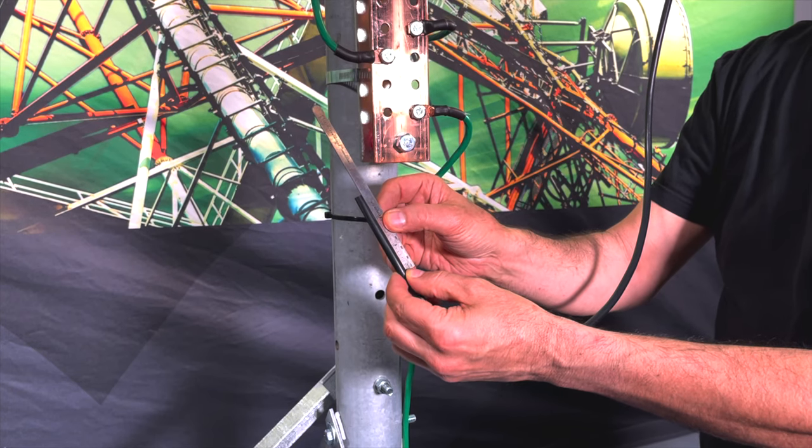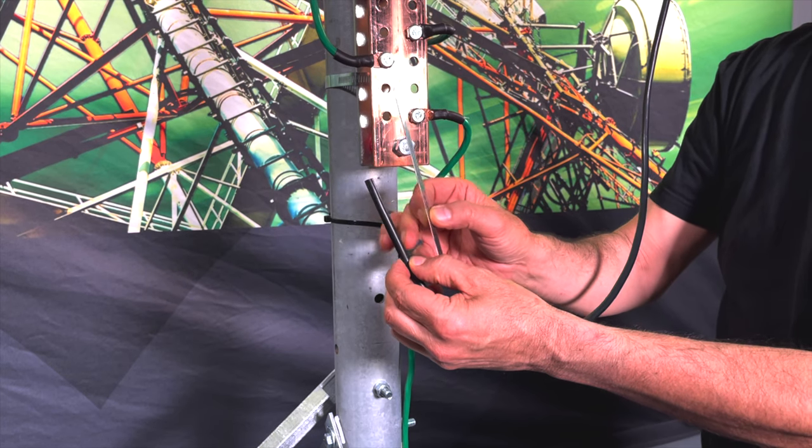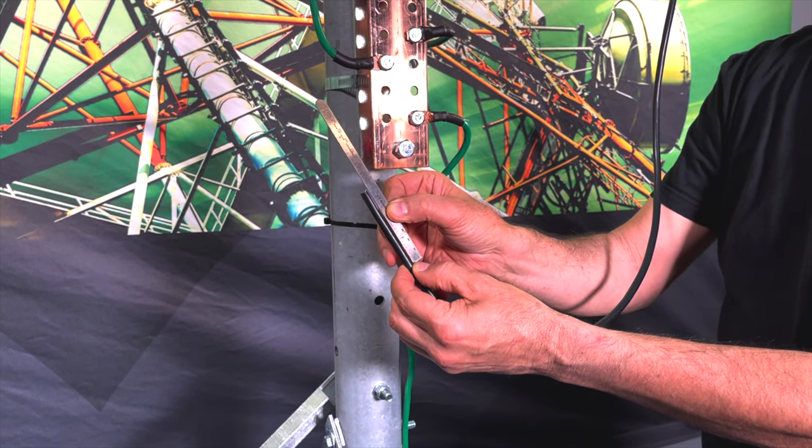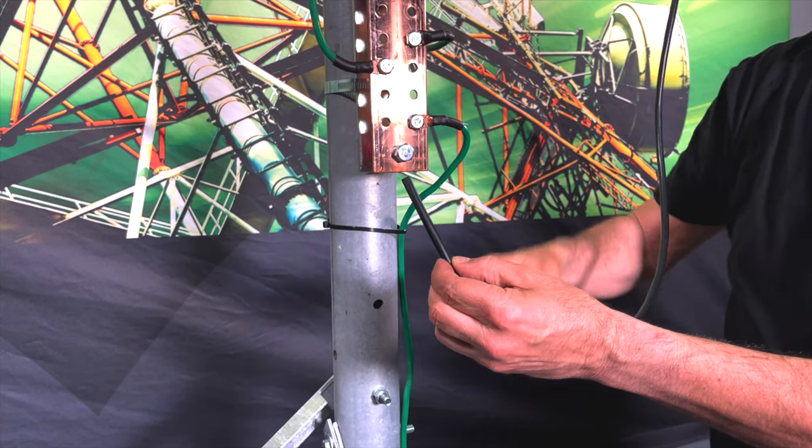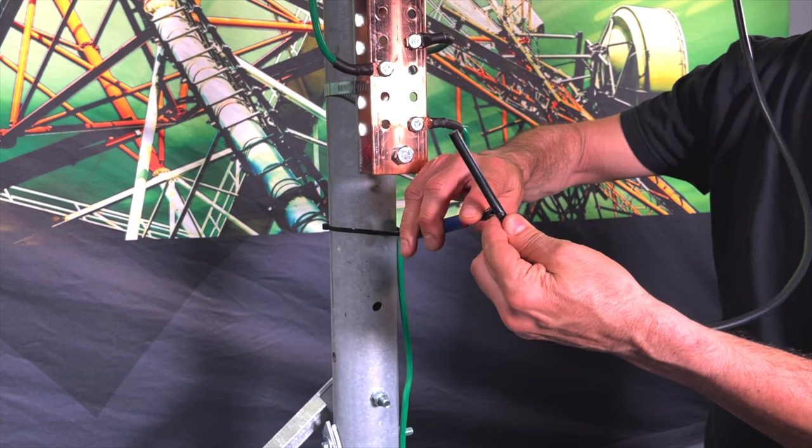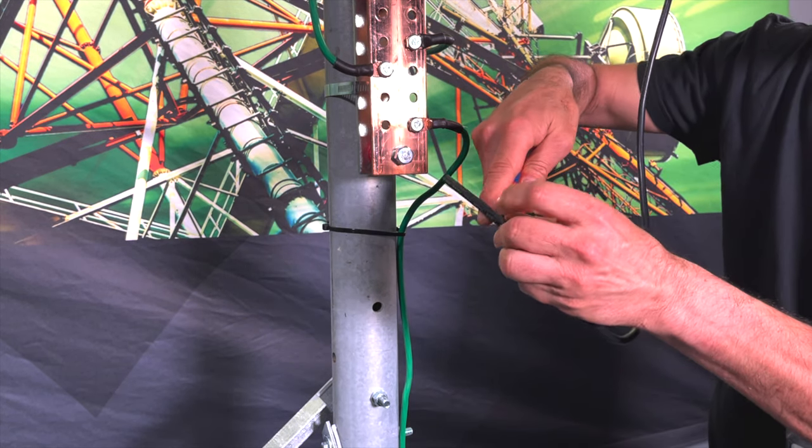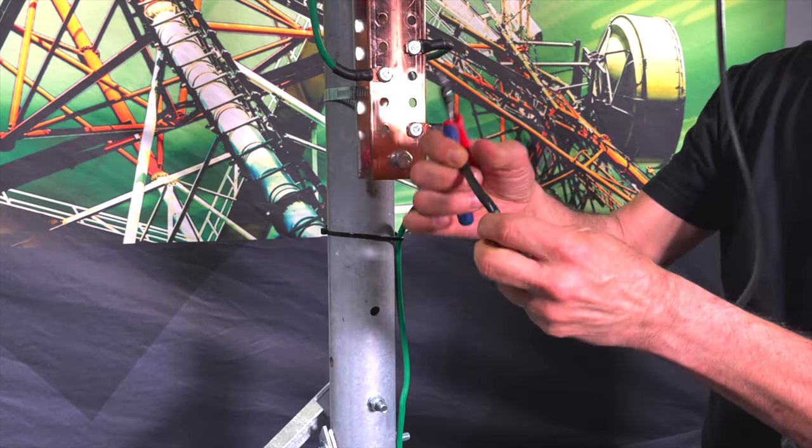The first step is to strip back three inches of insulation, this black jacket, from our DC power wire. I've got out my ruler, and I've measured back three inches. When you score it around here, you just want to cut the outer jacket. Bend this a few times, and that will expose the inner braid.